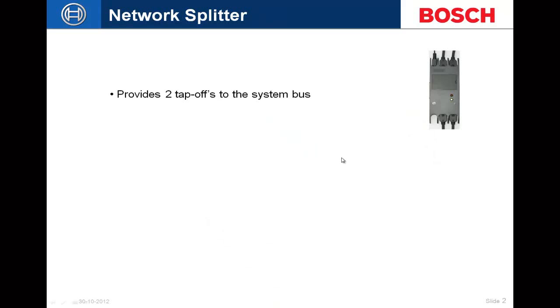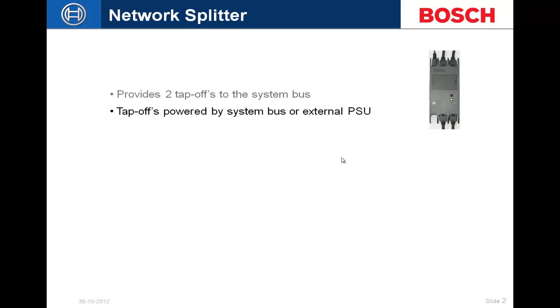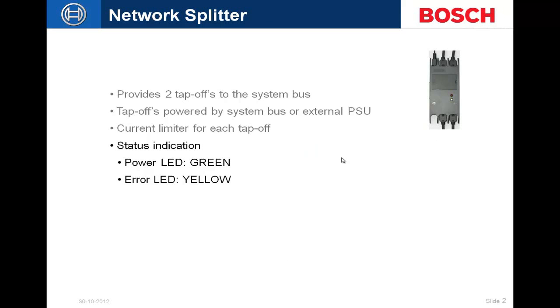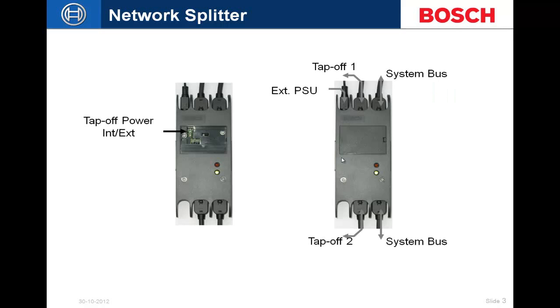The fiber splitter provides two non-redundant tap-off points from the system bus. If you have a redundant loop system and need to tap off to two non-redundant areas, you can put a splitter in the line and get a break-off onto two separate fibers. There is a power limiter that can be enabled for each tap-off point, and an external power supply is available to power the two tap-off points if the internal power supply within the network controller nears its load limit.